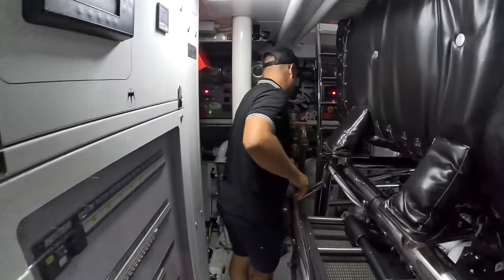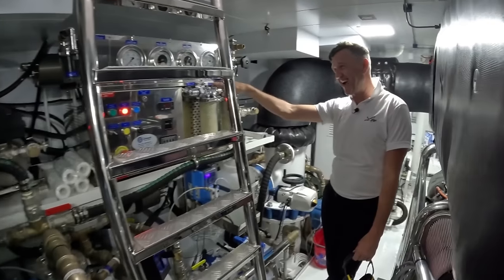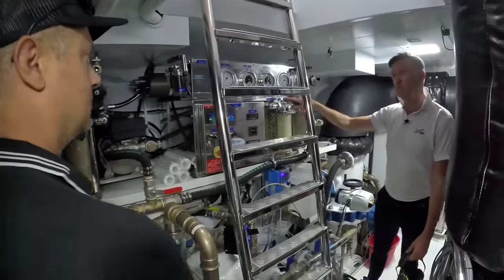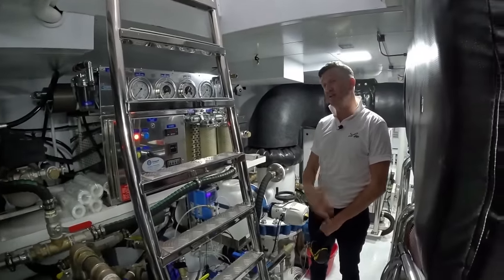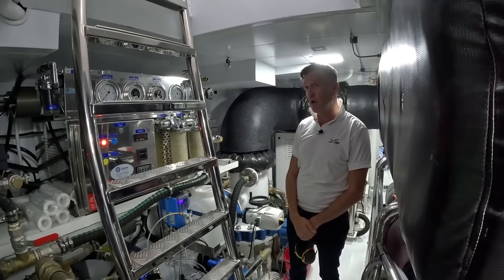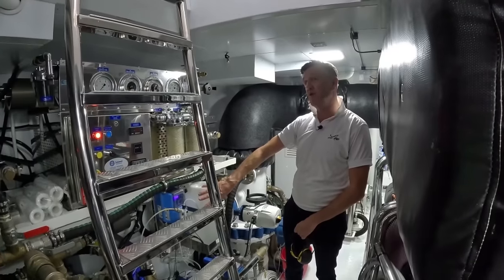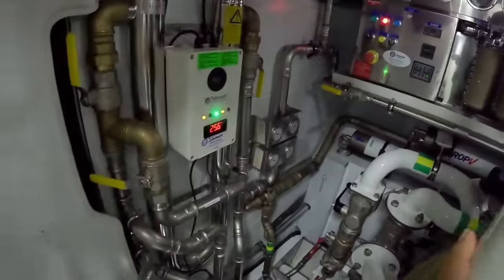The chillers are pretty quiet. Over here we have two Idromar 9000 series watermakers — reverse osmosis plants. Because we have two swimming pools and sometimes up to 12 guests and nine crew, that's a lot of fresh water. Pool water needs to be dumped every two to three days even though it's chlorinated. These units produce 800 liters of water per hour, with a self-dosing unit that doses silver ions and Katadyne into the system to remineralize the water, and a UV system for the final filtration.